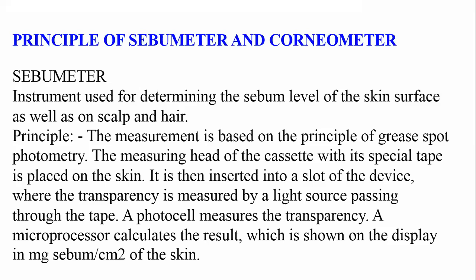The measuring head of the cassette with its specific tape is placed on the skin to collect the sample of sebum. After that, this cassette is inserted into the device, and it will measure the amount of sebum. The principle is similar to a spectrophotometer — the instrument measures the content on the basis of the intensity of light passing through the sample. After placing the cassette inside the instrument, a beam of light passes through the tape in the cassette, and the photocell measures the transparency. A microprocessor calculates the result and displays the content of sebum in milligrams per centimeter square of skin.